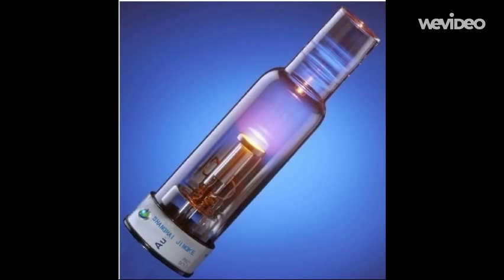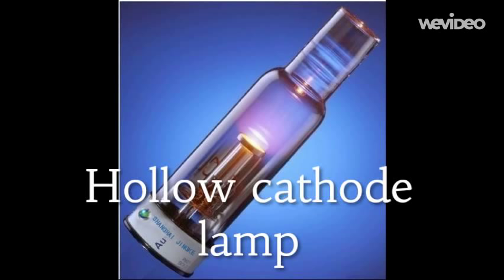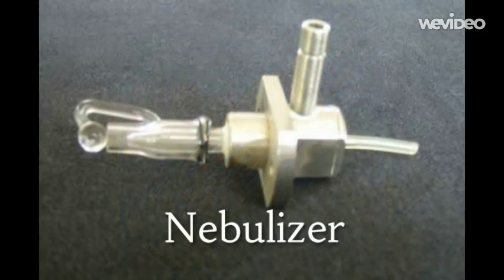The following components make up the AA instrument. The hollow cathode lamp is the source of analytical light line for the element of interest. It emits a constant and intense beam, and it must contain the same element as the analyte being tested. The nebuliser is used to suck up a liquid sample at a controlled rate, creating a fine aerosol spray for introduction into the flame source.